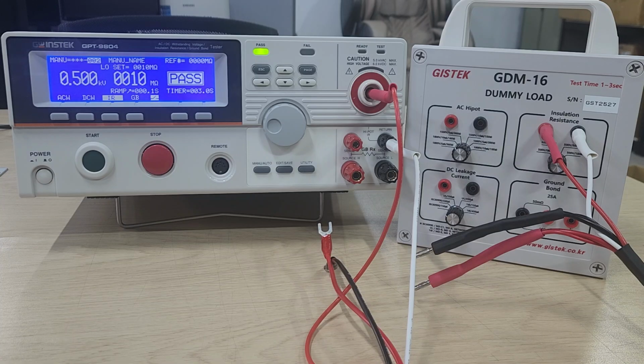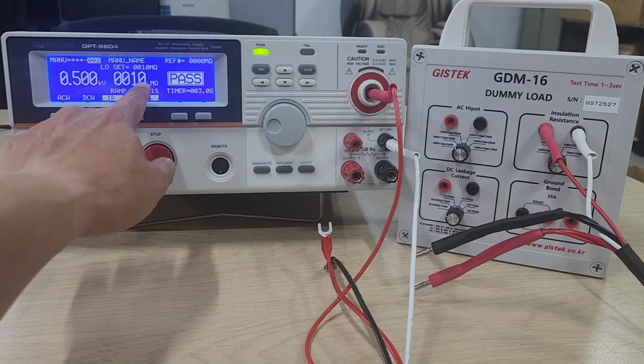Perform the inspection and check with the inspection result whether the DC insulation resistance tester measures the value set at the dummy load closely. The test result may vary depending on the resistance value error of the dummy load, output error of the DC insulation resistance tester, and measurement error. But typically the error may be around 0.1 megaohm at 10 megaohm.